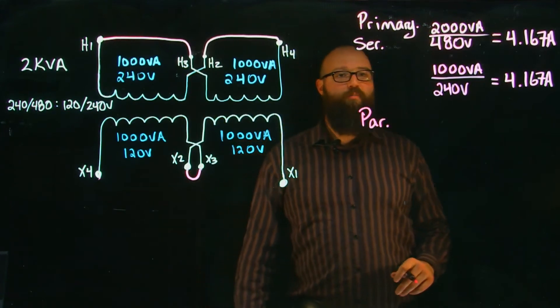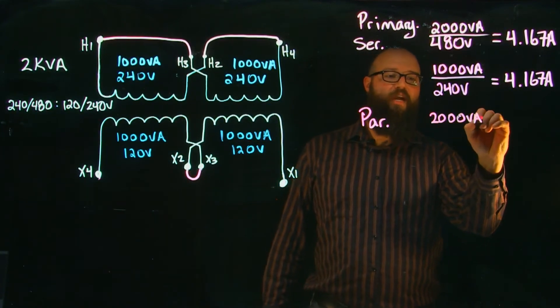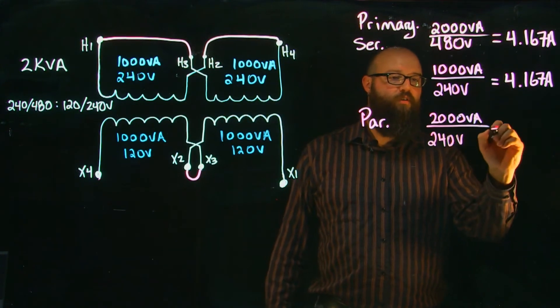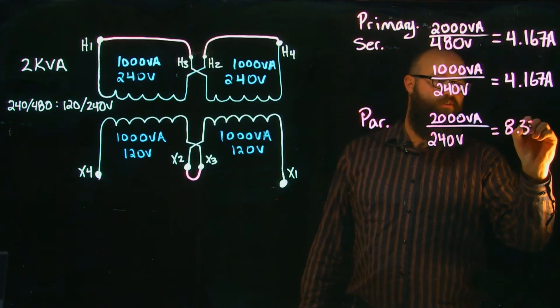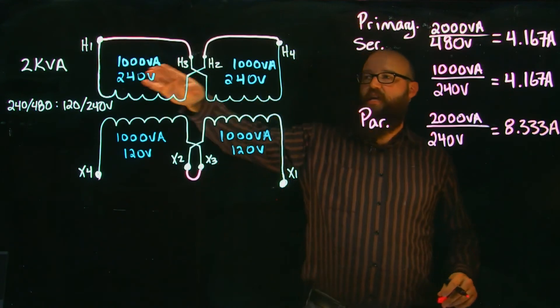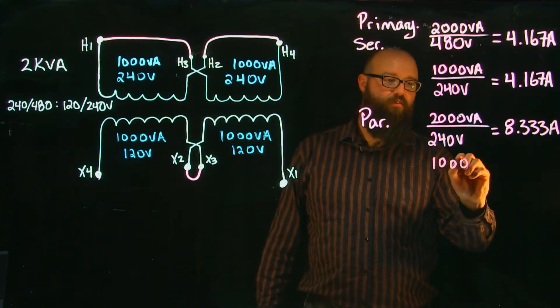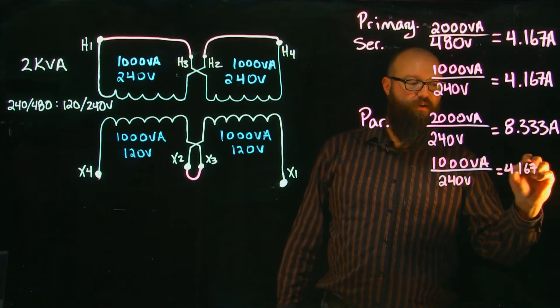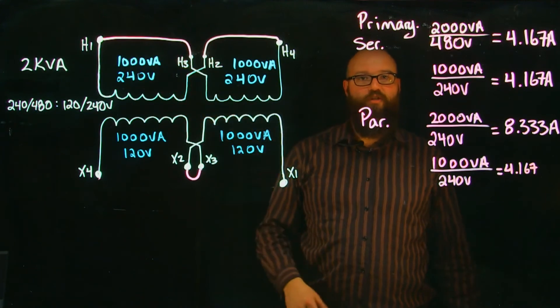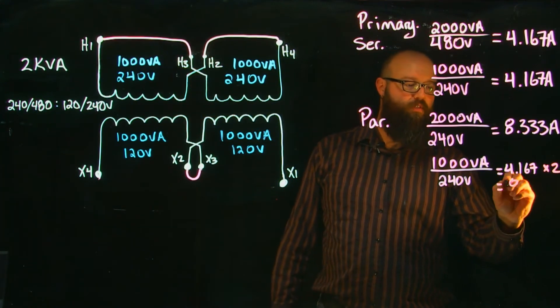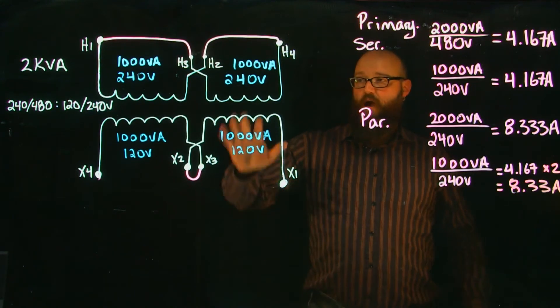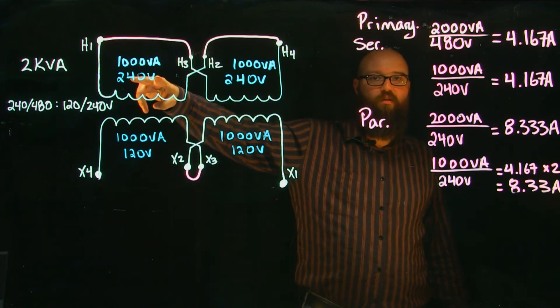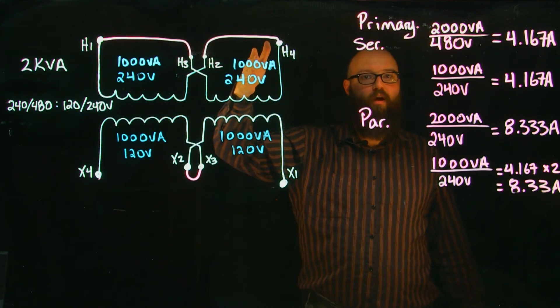For the parallel primary connection, we have 2000 VA divided by the parallel voltage of 240 volts, giving a current of 8.33 amps. Looking at individual coils: 1000 VA divided by 240 volts equals 4.167 amps, but because current is additive in parallel connections we multiply by two, which again gives us 8.33 amps. Both methods — total VA over total voltage, or individual coil calculation times two — agree.